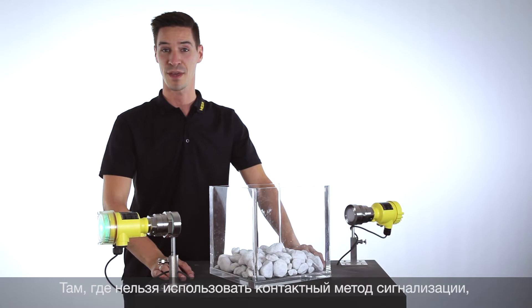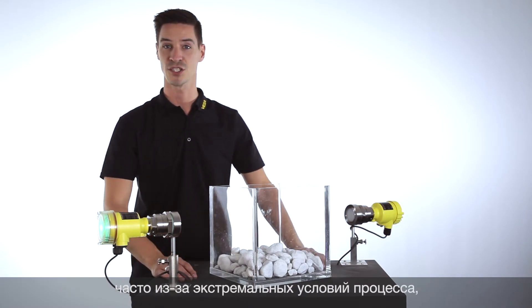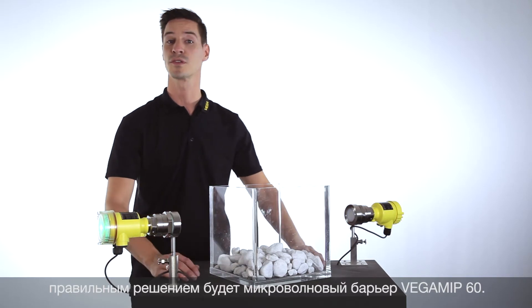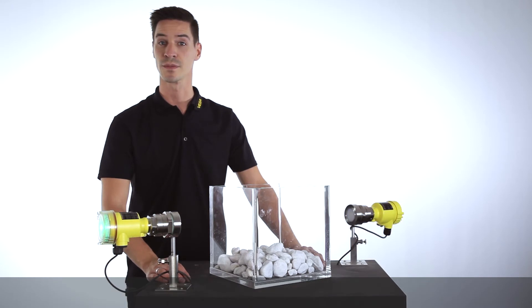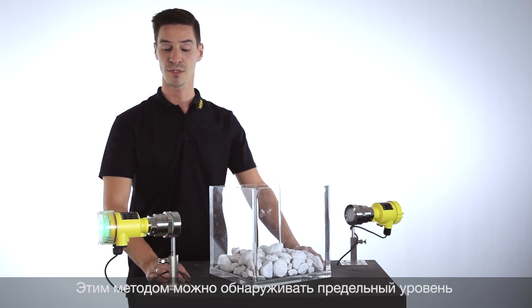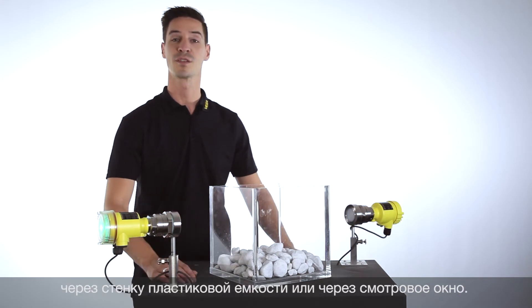Whenever a medium-contacting method is not possible for detecting point level in a bulk solid application due to rough process conditions, the microwave barrier VEGAMIP 60 is the right solution. This measurement principle can even measure through a plastic vessel or through an inspection window.